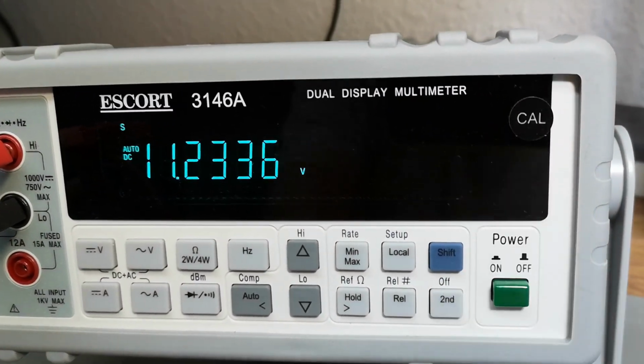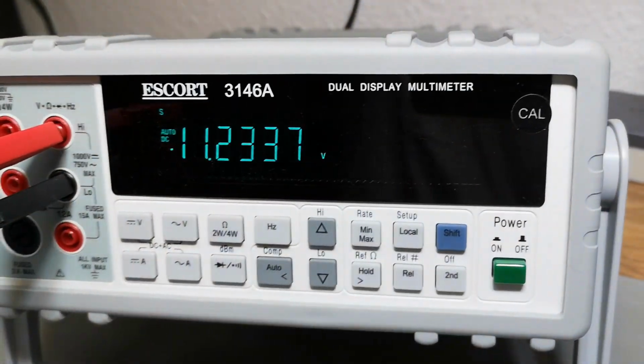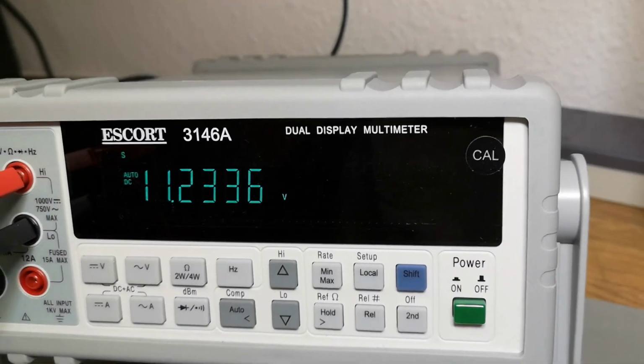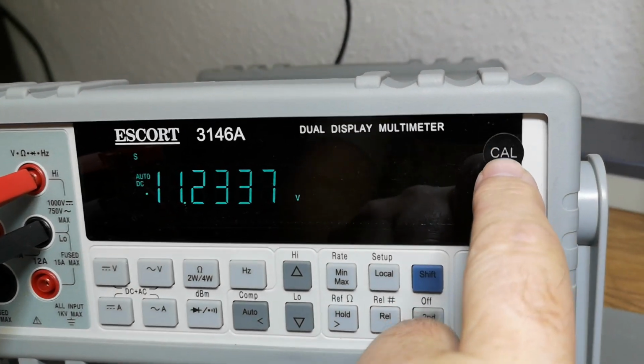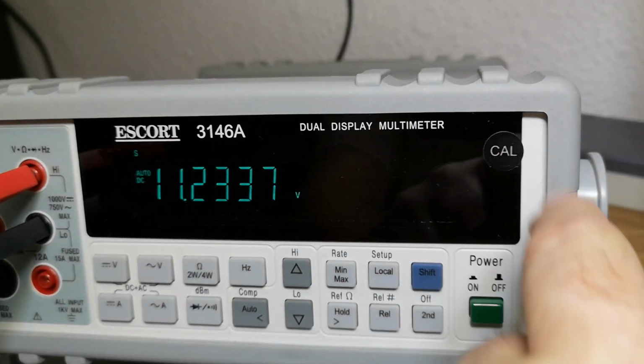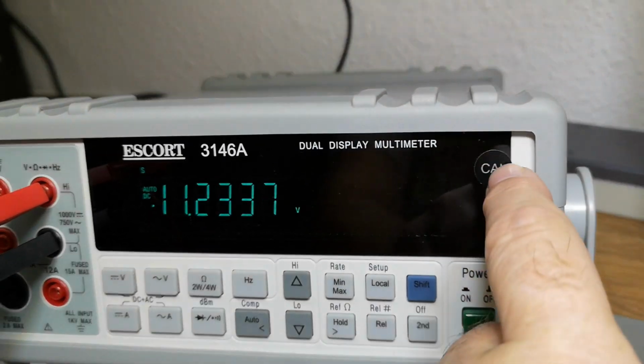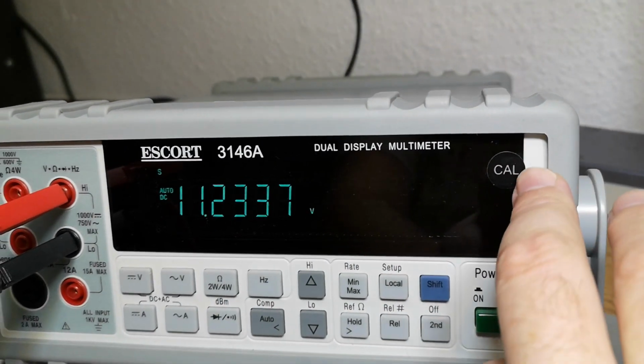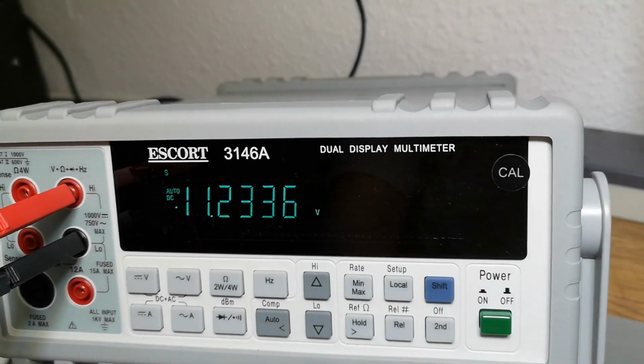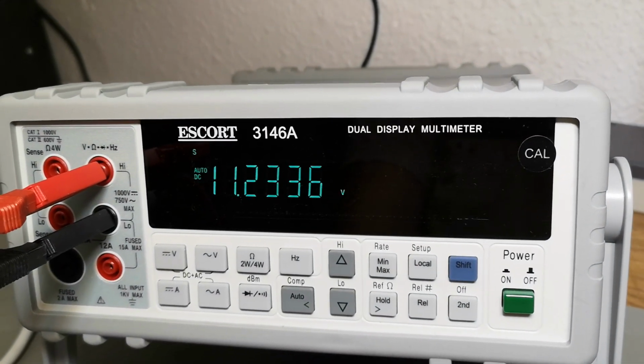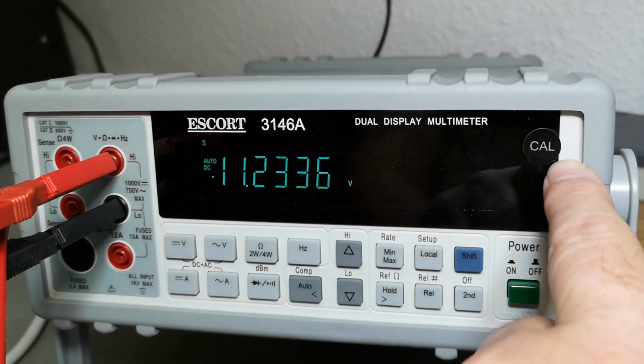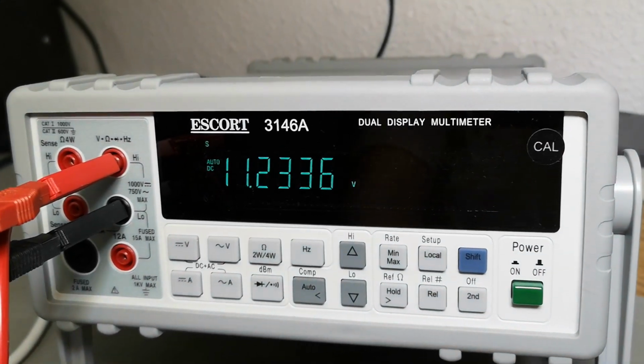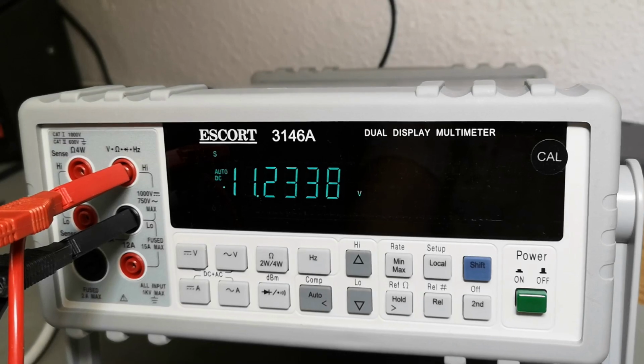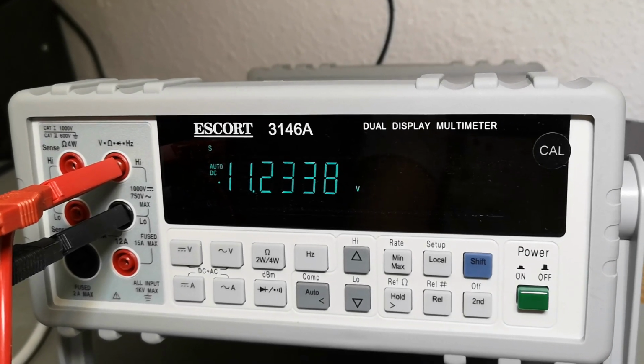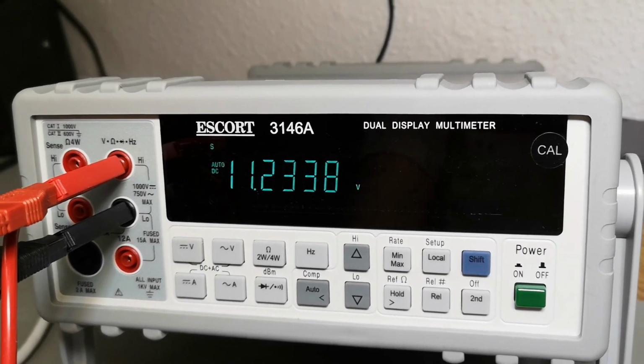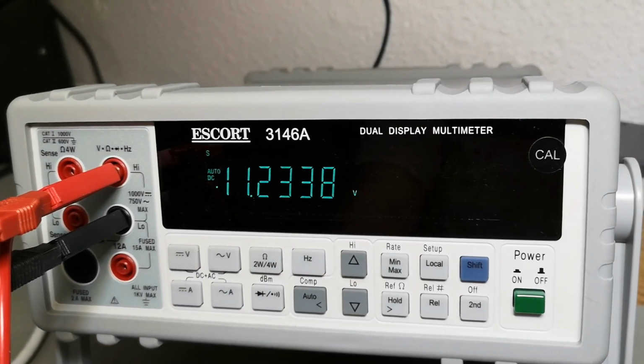That is this Cal sticker. And on the Escort unit, this Cal sticker actually hides a tiny little hole where you're supposed to stick a paper clip or something like that to activate a little switch. And once you do that, you're now in calibration mode. So don't do that unless you have the calibration instructions and you are ready to do the calibration and all that kind of stuff.